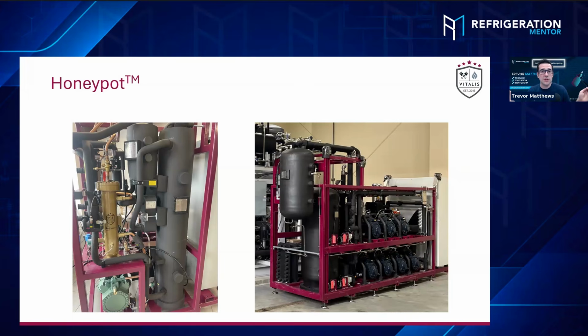So now we're still pulling out all that moisture, anything in there. The other valves will be open at that time. So the oil will feed. No, you will still have closed while you're under vacuum, right? So you would isolate the whole oil reservoir. You would pull your oil in with the vacuum pump as soon as you reach the middle cyclers, maybe a little on top, if you already assume the system is still saturating. But you don't want to fill that completely up, right? You want to have some sort of buffer to separate the CO₂ while returning the oil, but also to have some fluctuation for oil level, basically, without draining that back through the equalization line.